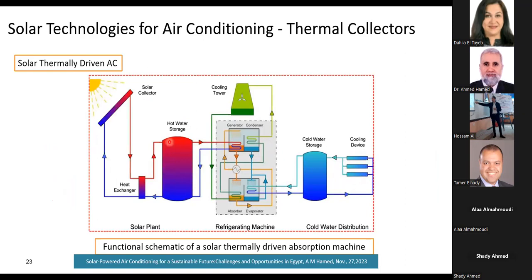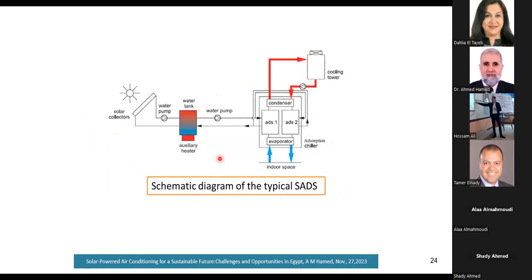As a result of the intermittent nature of solar energy, this system must be equipped with storage methods, whether for heating or cooling, to compensate for the intermittency of the solar radiation. I think there is no need to explain in detail the operation of the absorption system in this presentation. Another version is the closed adsorption cooling system that may use silica gel as adsorbent and water as refrigerant. And of course, the evaporator temperature in this case is limited to from 5 to 7 degrees Celsius. This is because, of course, water is the working fluid.